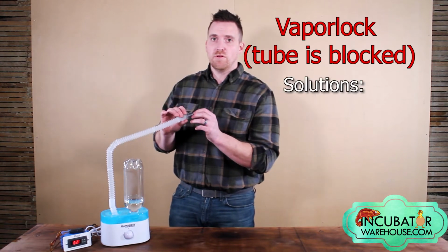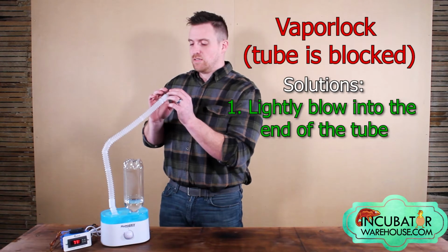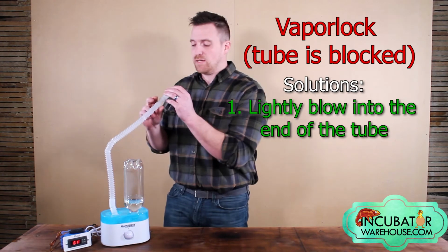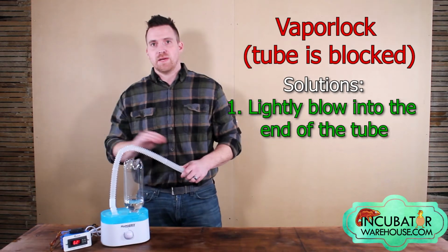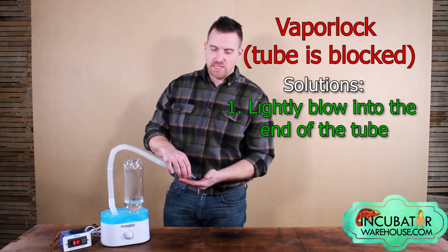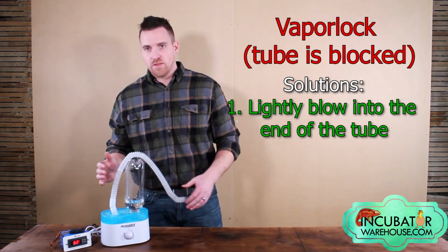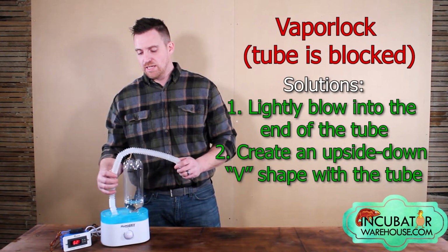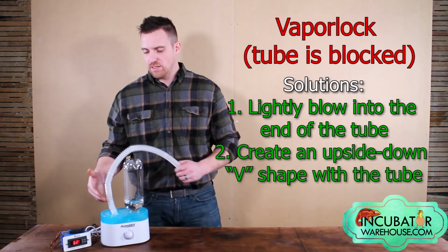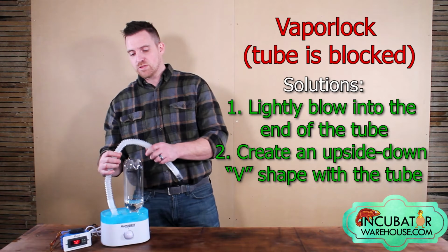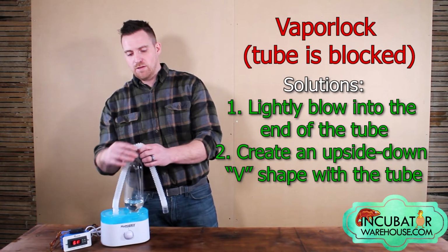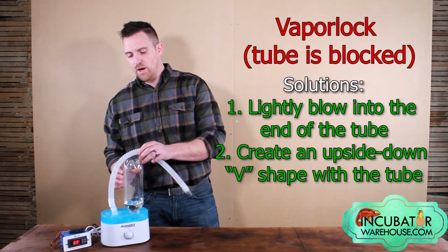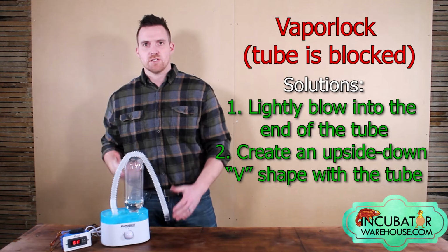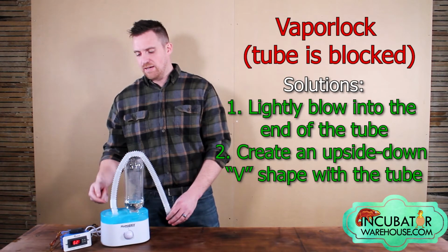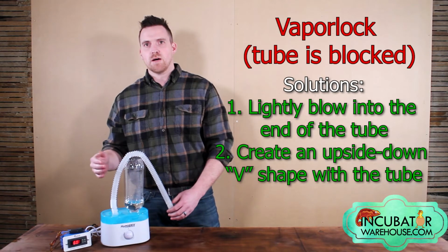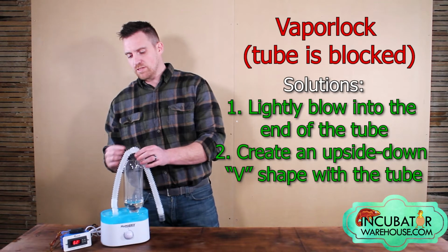Very simple solution. Remove it from the incubator, blow gently down the adapter nozzle back towards the base of the Humidikit. This should break up any vapor lock that's occurring anywhere between the tube, and you should then see humidity producing out the base. The other option is to make sure that your tube is not laying sideways or have any droops in between the Humidikit base and the incubator. We always recommend doing a mountain-like shape with the tube, or even resting it over the bottle as a stand to help make sure that the tube is in a vertical upside down V shape or a mountain peak shape. This will also help prevent vapor lock from occurring, and it will allow the water to drain back down into the Humidikit base.